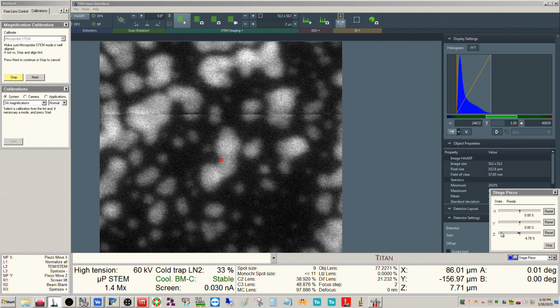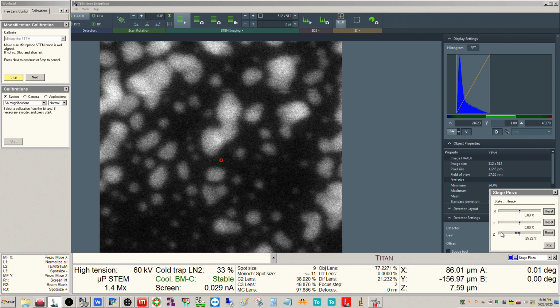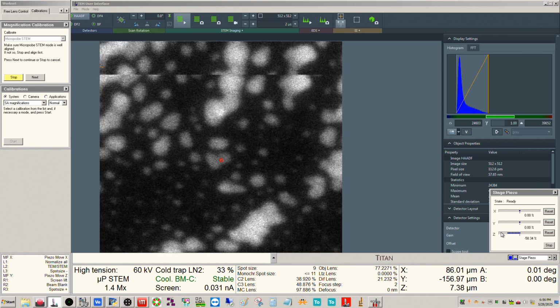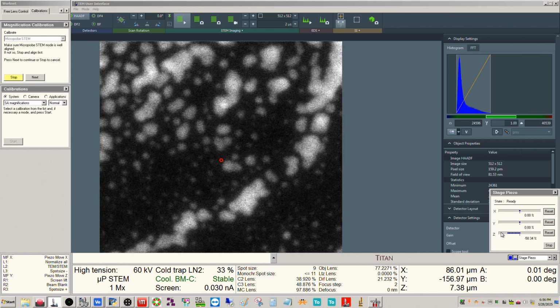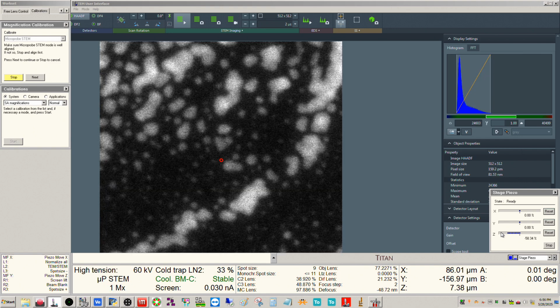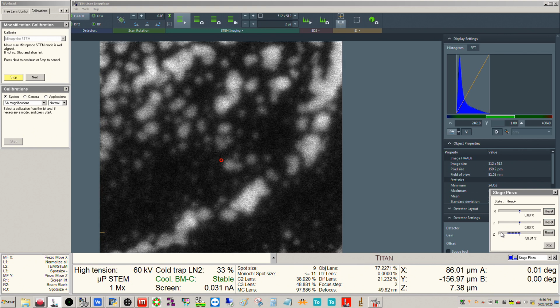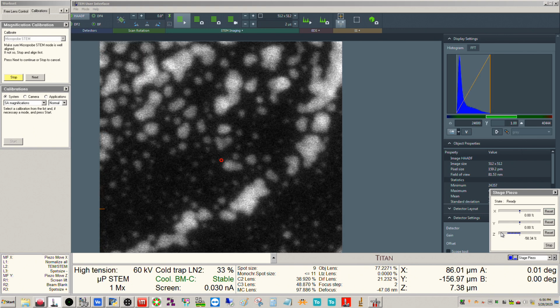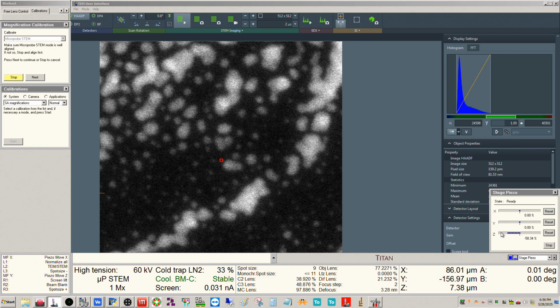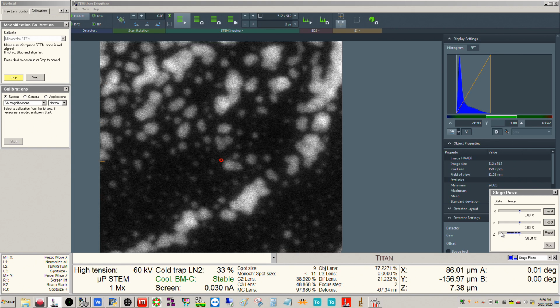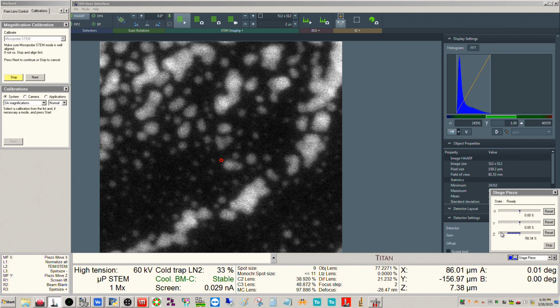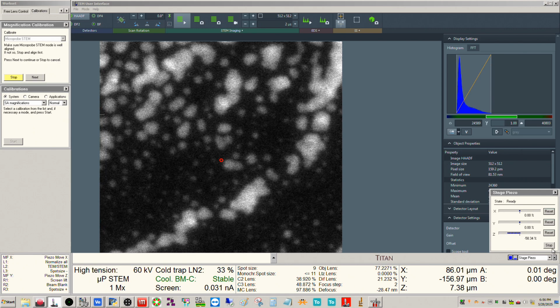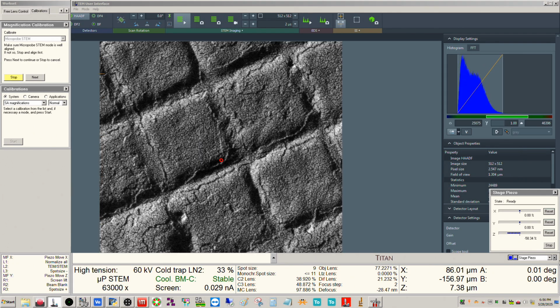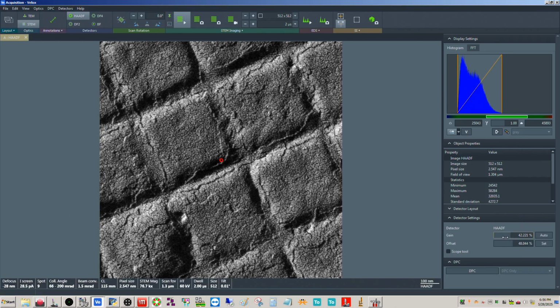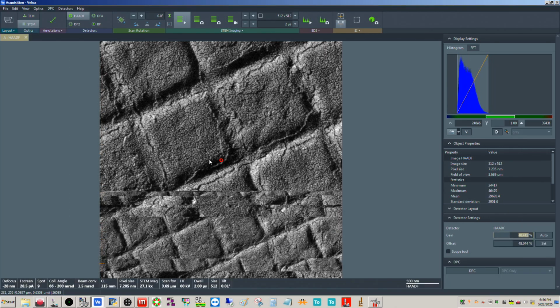In nanoprobe, or microprobe, your depth of field is pretty high here. We're not going to get atomic resolution, obviously. Let's see here, as far as the focus. Yeah, so we're getting good focus with just a few tens of nanometers of focus. If there was any astigmatism in the image, we could correct that, but that looks okay. All right. We might have a little too much gain, but we'll leave that there for now.